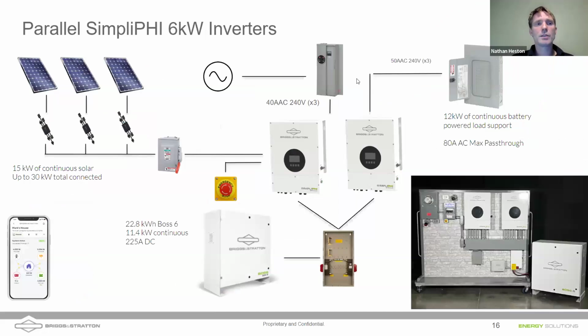I'm just pointing out these loads as we go into systems. So let's look at an example of a parallel SimpliPhi inverter. This is a little bit small for doing whole home backup. Both of these inverters have a maximum of 40 amps of pass-through, so you could potentially get 80 amps of load support in your loads panel of the home. But 80 amps is on the small side. That's under 20 kilowatts of power available. So it's not ideal for a whole home backup.